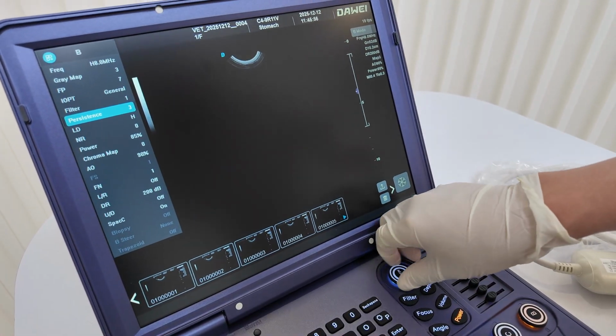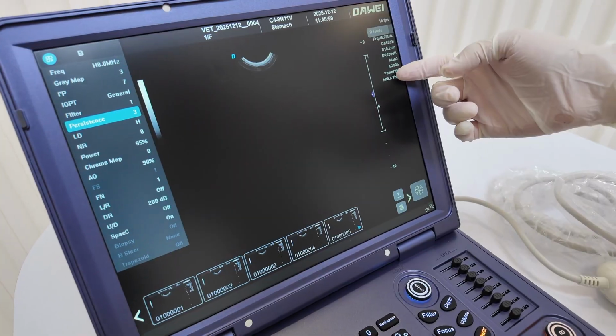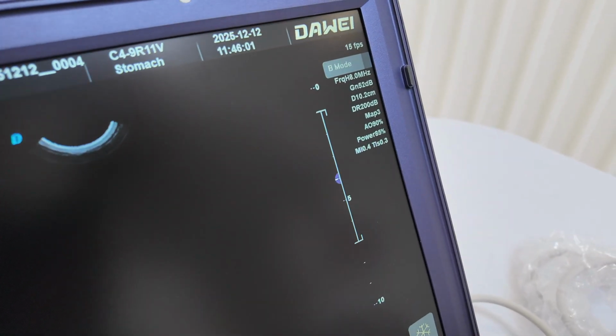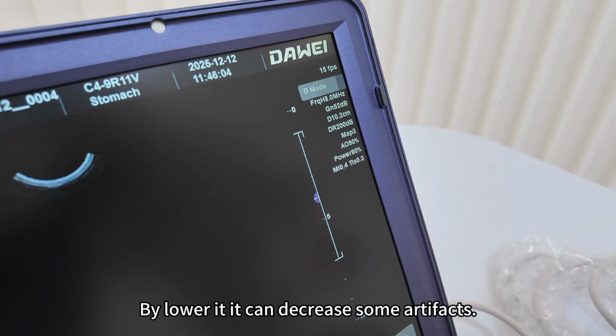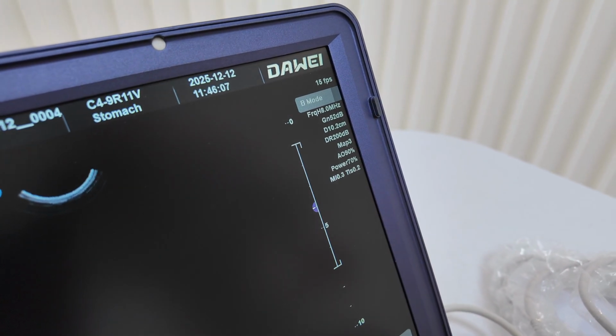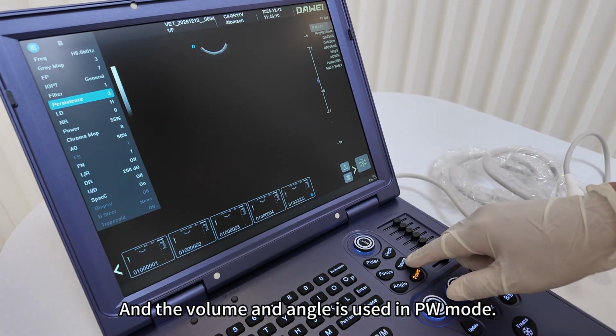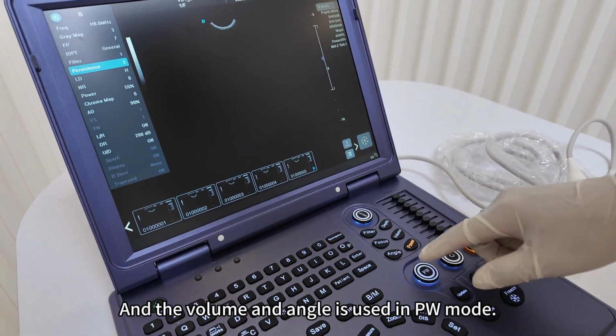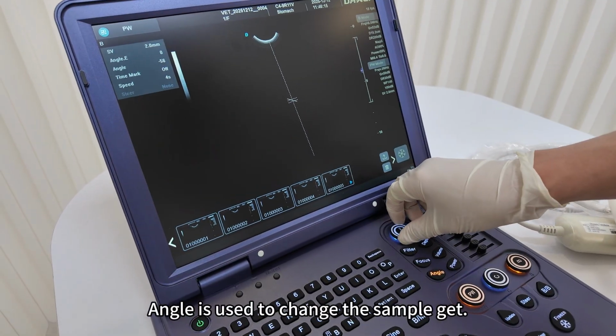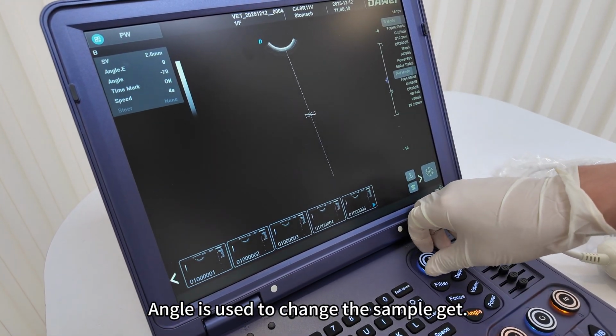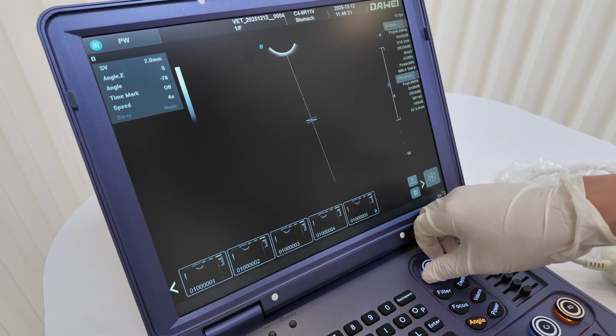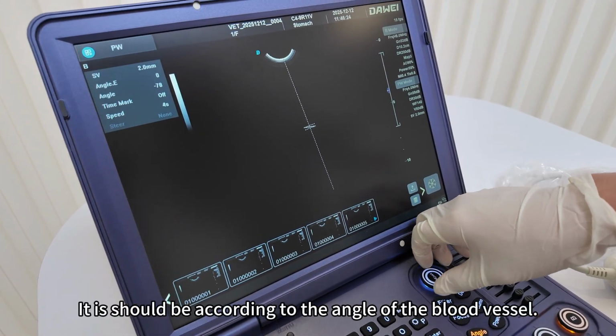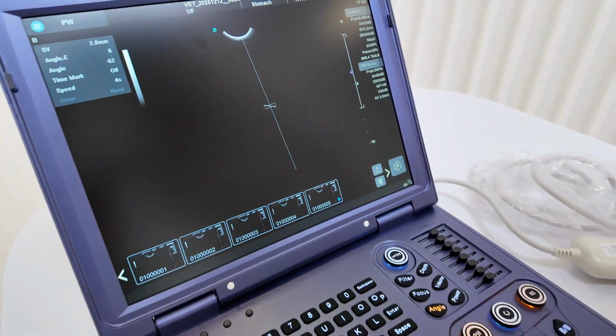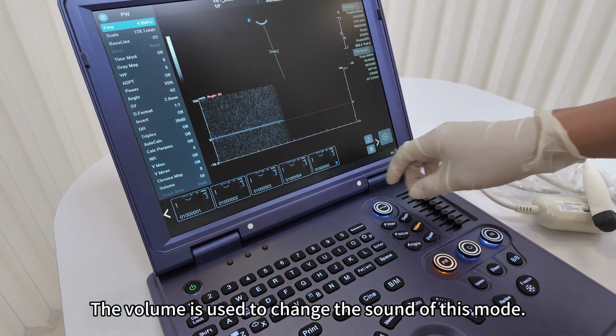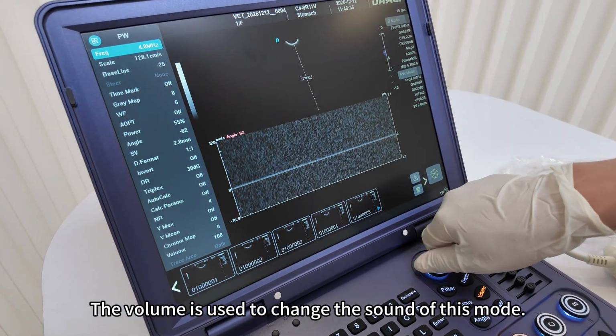Next is power. We can change the power of the probe. Here, the figure shows here. Lowering it can decrease some artifacts. And the volume and angle are used in PW mode. Angle is used to change the sample gate. It should be set according to the angle of the blood vessel. The volume is used to change the sound of this mode.